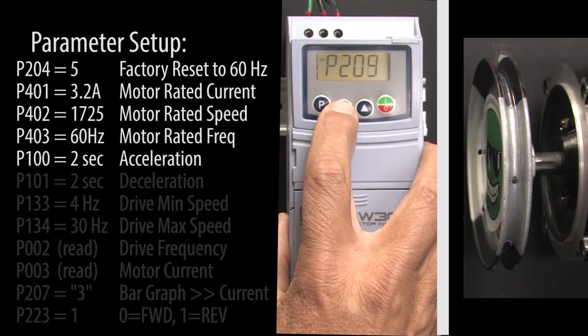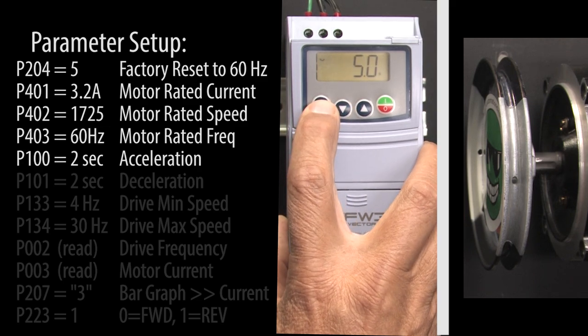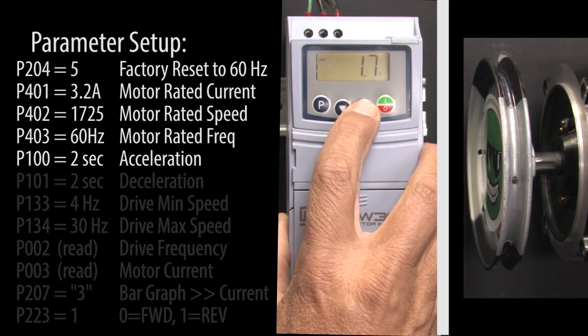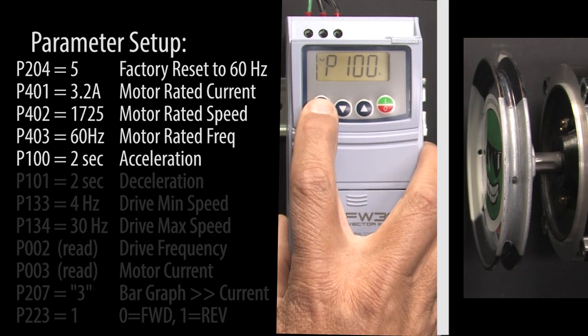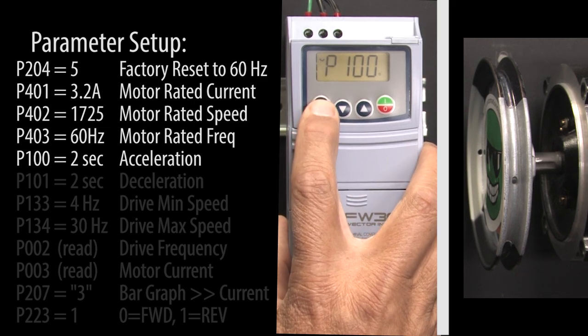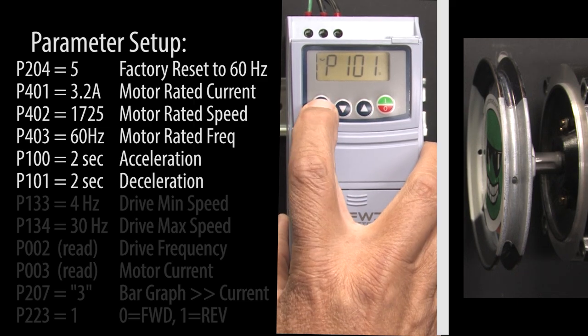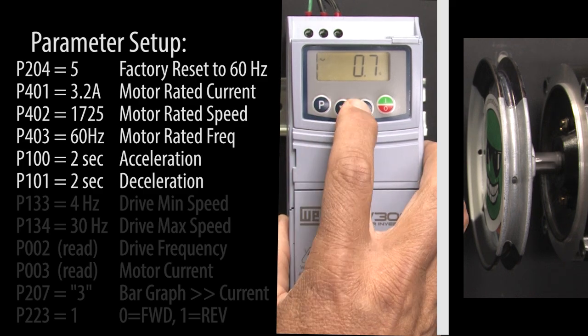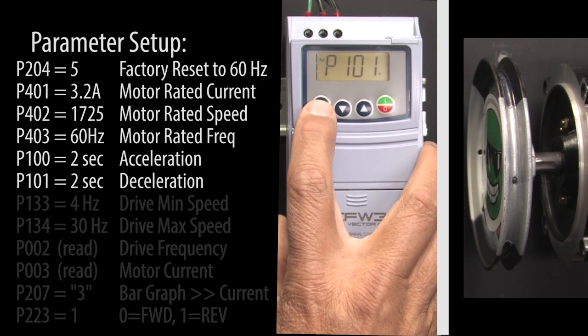Scroll to the acceleration parameter, which is 100. Hit P to change it — I'll change it to 2 seconds and hit P to accept that value. Scroll to the next parameter on our list, hit P and change the deceleration to 2 seconds and hit P to accept that.